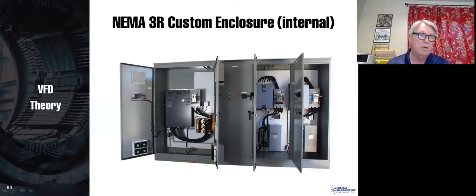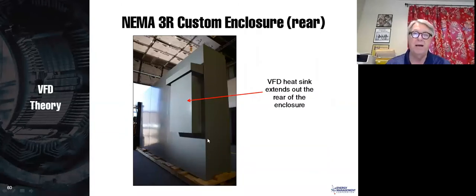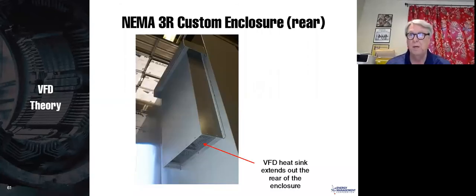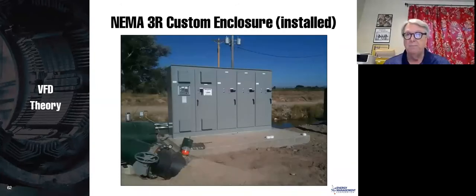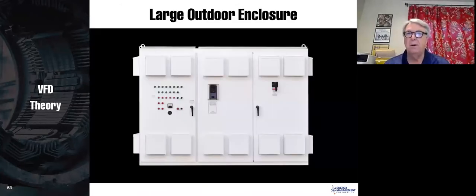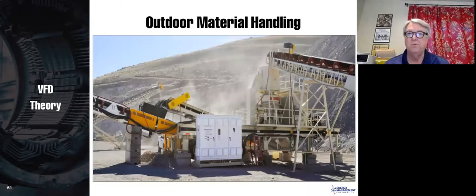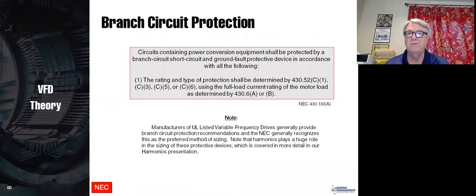And you'll notice in this case, the drive has the heat sinks poking out through the back of the enclosure. That's why you can get by with such small fans here. And if you look on the back, the heat sinks are poking out through the back of the enclosure. And that's a way of still keeping the interior very clean while allowing the outside fins to be cooled. It's a little picture from the bottom, and there it is on a pad. This is a pumping station. There's a large outdoor enclosure, and there's one in a fairly dusty facility.